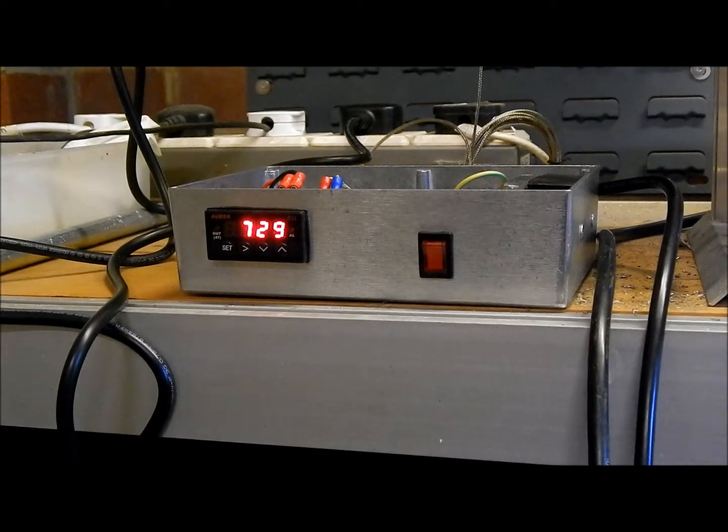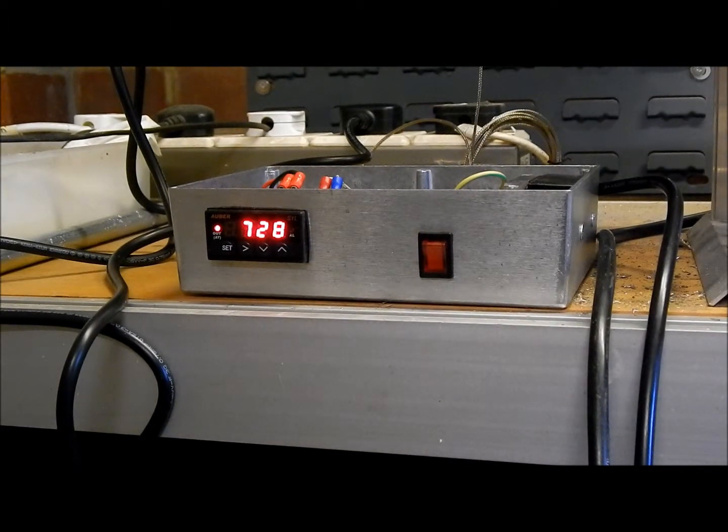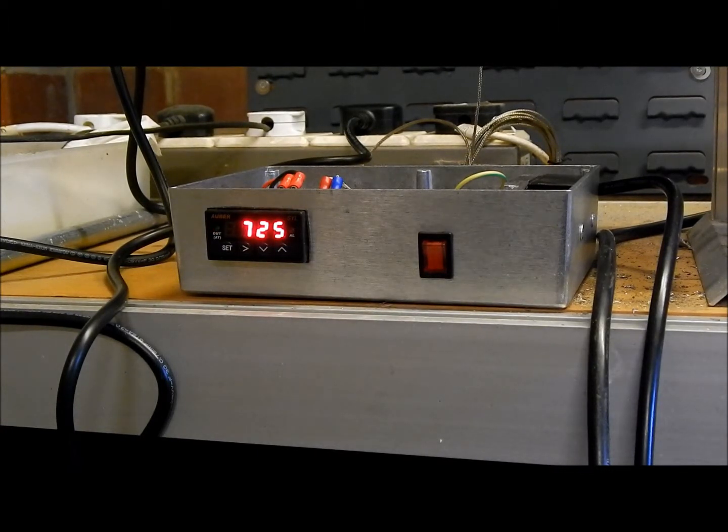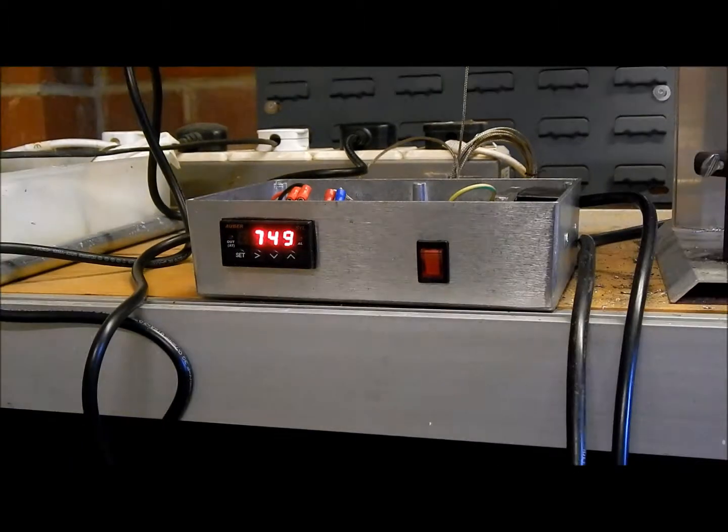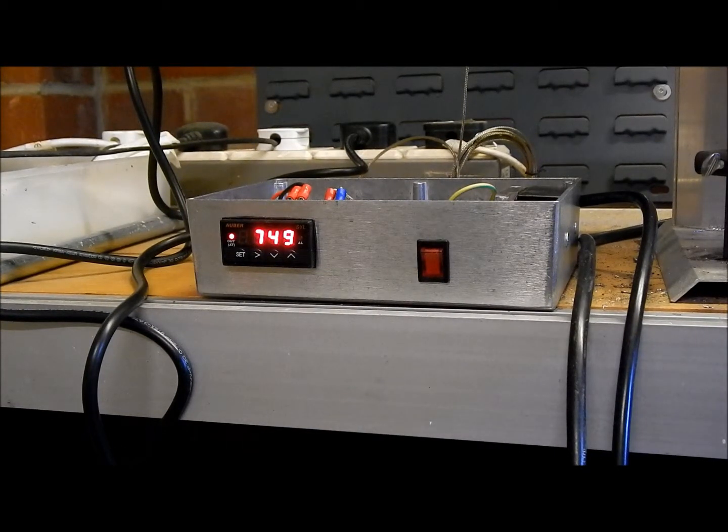On the third cycle it turns back on at about 720. It's now applying power more slowly as it reaches the final temperature. It's still auto-tuning, it's on the fourth cycle and it's now hunting about plus or minus 1 degrees around the set point.